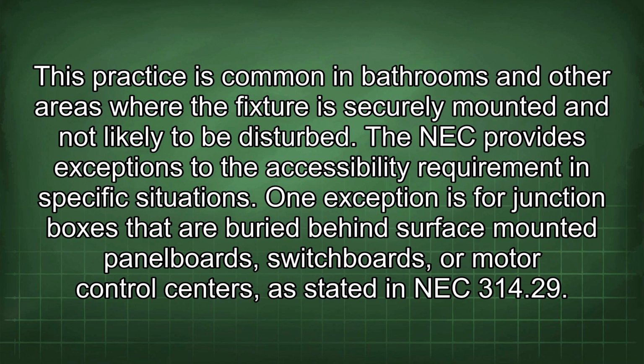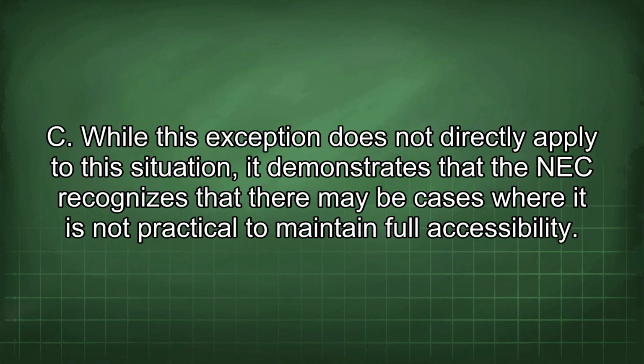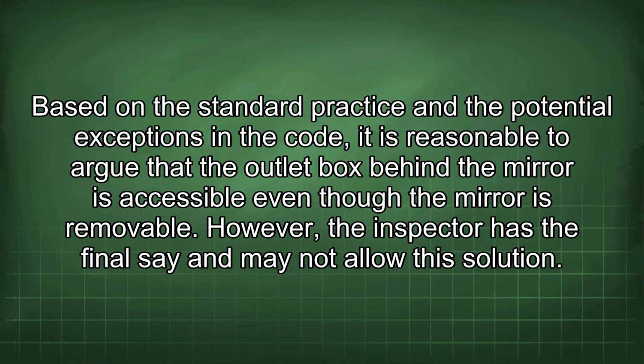One exception is for junction boxes that are buried behind surface-mounted panel boards, switchboards, or motor control centers, as stated in NEC 314.29. While this exception does not directly apply to this situation, it demonstrates that the NEC recognizes that there may be cases where it is not practical to maintain full accessibility. Based on the standard practice and the potential exceptions in the code, it is reasonable to argue that the outlet box behind the mirror is accessible even though the mirror is removable. However, the inspector has the final say and may not allow the solution.